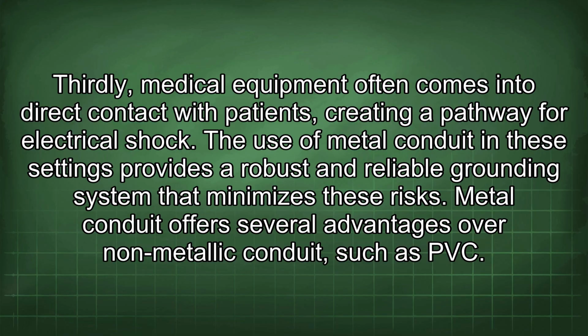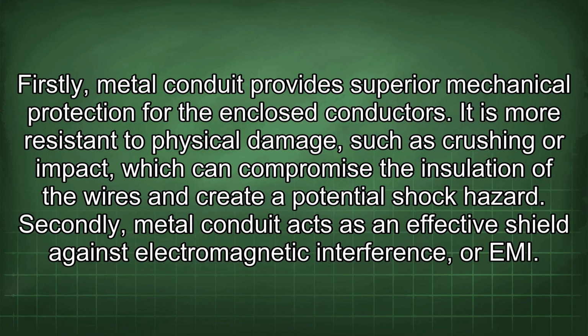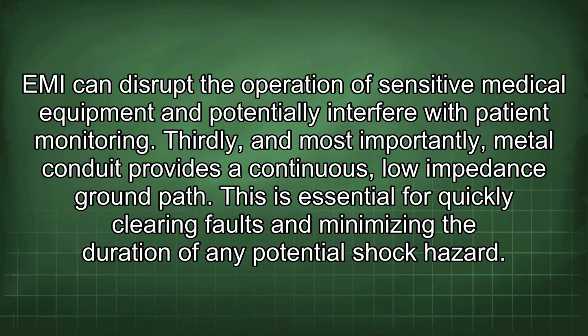Metal conduit offers several advantages over non-metallic conduit such as PVC. Firstly, metal conduit provides superior mechanical protection for the enclosed conductors. It is more resistant to physical damage such as crushing or impact, which can compromise the insulation of the wires and create a potential shock hazard. Secondly, metal conduit acts as an effective shield against electromagnetic interference, or EMI. EMI can disrupt the operation of sensitive medical equipment and potentially interfere with patient monitoring. Thirdly, and most importantly, metal conduit provides a continuous, low-impedance ground path. This is essential for quickly clearing faults and minimizing the duration of any potential shock hazard.